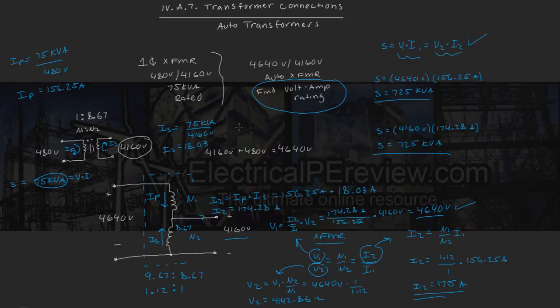For more practice, I challenge you to use this same configuration, but instead make it a step-up transformer. Redo the problem and connect your windings. This time, look at it going this way. You'll notice that the direction of all of your currents are going to change. Since you're stepping up now from 4160 to 4640, you're going to have an input current, you're going to have a winding current going down, and a winding current going up. This is going to be your new output current. This is going to be your new input current. And this would be your V2. This would be your V1.